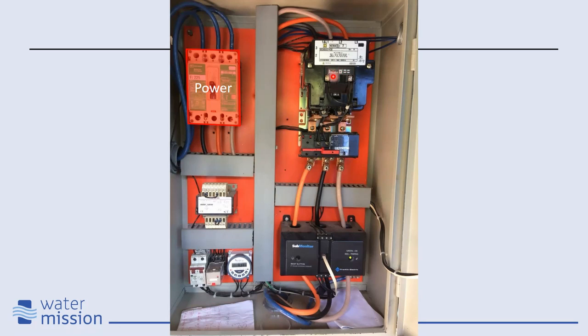Another feature, I said it has an OCP, Overcurrent Protector. And that is right here, and that is measuring the current on each line that's going over to the pump. And if it senses too much current or an imbalance of current, it's going to send a signal to the contactor to open, to turn off the pump.